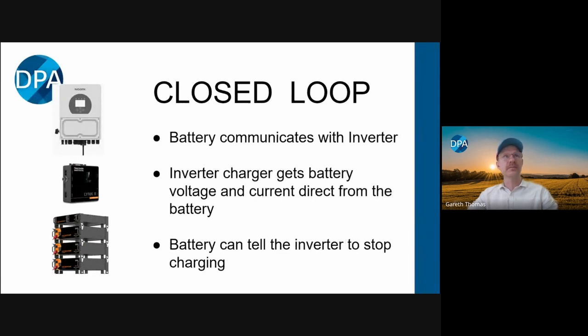When you have a closed loop system, that means that the battery bank is communicating directly with the inverter. So what it's doing is telling the inverter, this is the maximum voltage I want to be, this is the maximum amount of charge current I want to receive, and this is the maximum amount of discharge current that I want to give out. And those values are dynamic. So as it gets towards the bottom, it might throttle off that discharge current because the battery's getting empty. And as the battery gets full, it might throttle off that charge current or reduce that charge voltage.